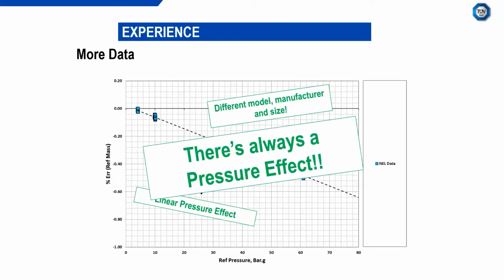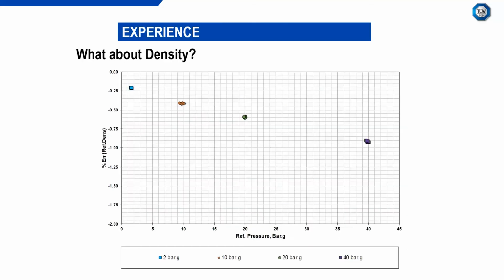Certain very small meters claim there's not a pressure effect. We've not done a great deal of work with the very small meters, and that's partly due to the limited flow range of this facility. We can operate from 0.5 to 100 litres a second. So below 0.5 litres a second, for these very small bore meters, we've not done a great deal of research. Partly just due to the fact that we don't have a very small facility that can operate at elevated pressures.